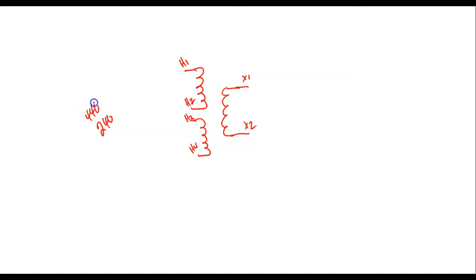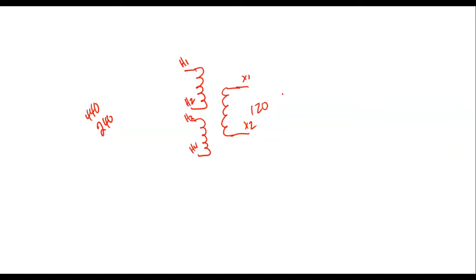On this transformer, I can bring in 240 or 440 volts and get 120 volts out, no matter which way I wire it. If I bring in 440, we want more turns on the primary than on the secondary, so we'd connect H2 to H3. We hook them in series because the current in the primary is going to be lower since we have a lot of windings on the high voltage side. This gives us a divide by 2. So for purposes, let's say this is 100 windings, this is 100 windings, and this over here is 50 windings.